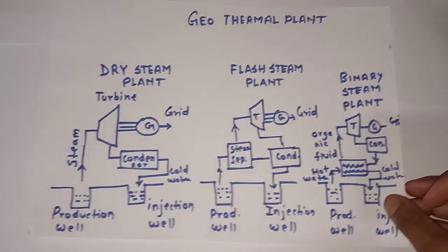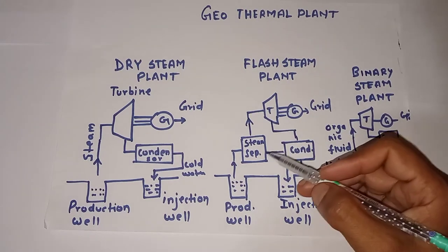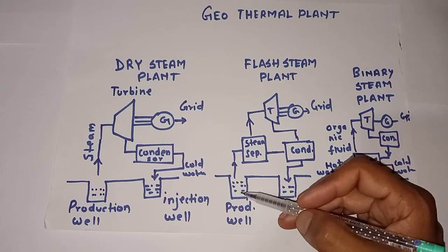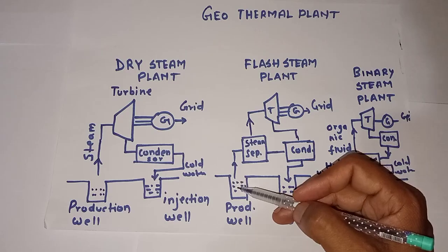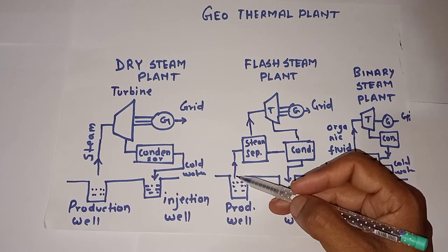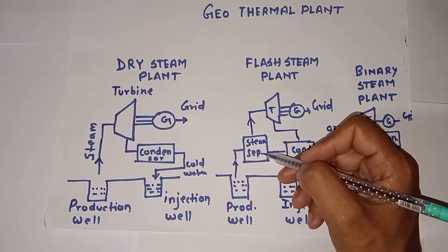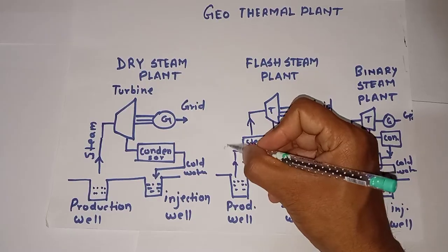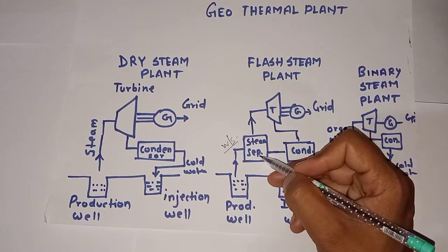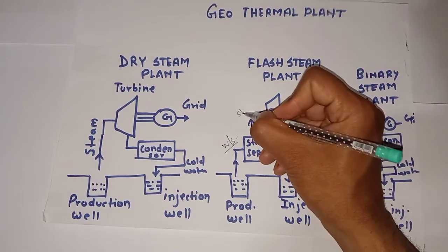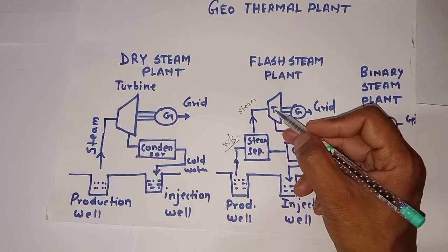The next type is called the flash steam plant. The difference from the dry steam plant is that an extra component is added. Whatever water and steam mixture comes up from the subsurface through the production well passes through a steam separator. The steam separator separates the water from the steam, and only the steam is sent to the turbine, where the turbine blades rotate.